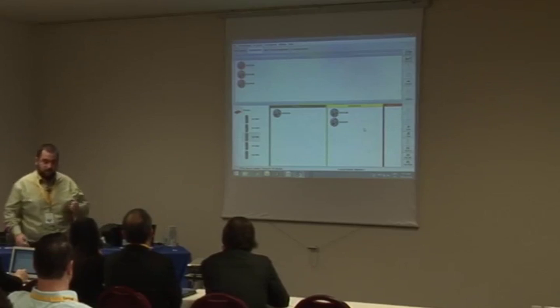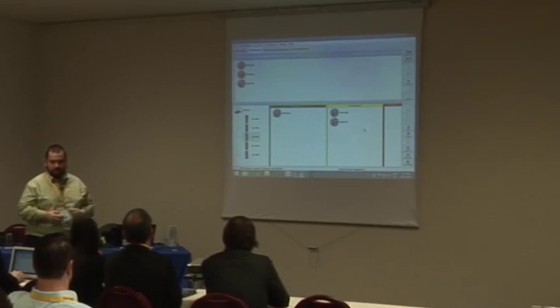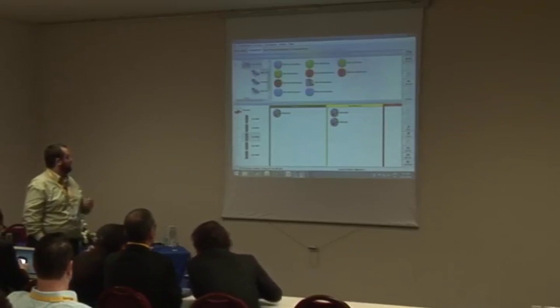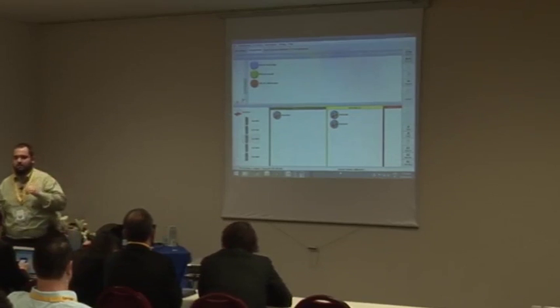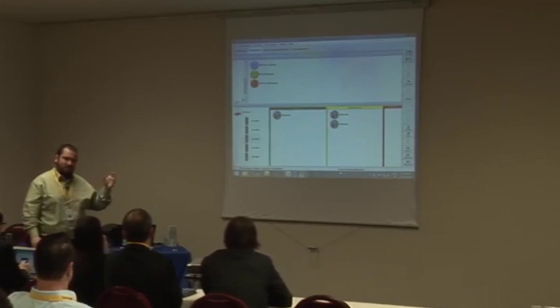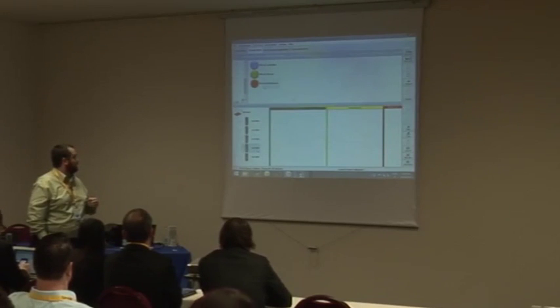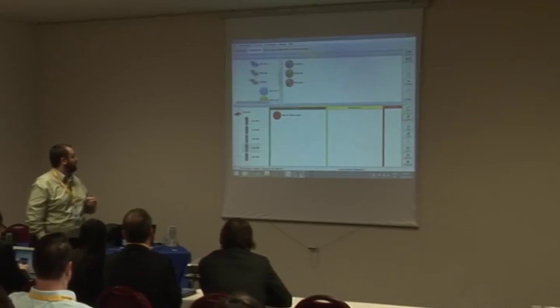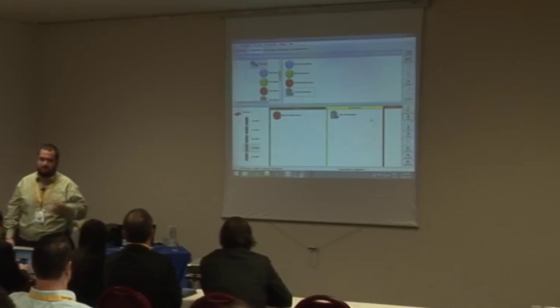Alternatively, if I want to be more granular — if I only want to receive a specific alarm from a specific bed — I can also do that. I can drill in to a specific alarm. Using an example from Pediatric Pod C, I have the individual alarms for that specific bed. I'll select another phone and say that I want to receive only the staff assist for that particular bed. And for Pod B, I want to receive the ventilator alert on a secondary level — so the assignment is very specific to the type of alarms in each particular bed.